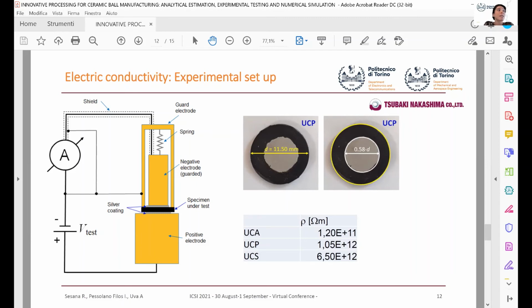Each specimen under test is placed upon the positive electrode, and the opposite side of the specimen is electrically connected to the negative electrode, which is guarded by a third electrode that collects leakage currents and excludes them from the current measurement path. A shielded cable connects the negative electrode to the ammeter. A spring is mechanically coupled to the negative electrode in order to ensure a proper contact pressure on the specimen. Then the resistivities reported in the table were calculated considering the test voltage and the measured current. Sample UCS exhibits the highest resistivity, while sample UCA is the one with the lowest resistivity.